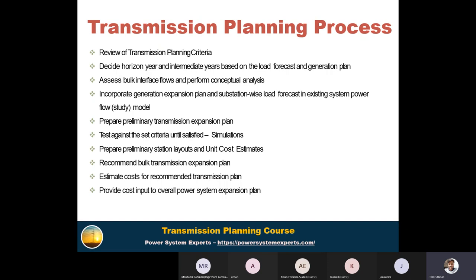But at first, we should have an idea of a preliminary transmission expansion plan, and then test it against the set criteria. So test all these model cases in the software, PSS/E, against those criteria, steady state as well as transient. After that, prepare preliminary station layouts and unit cost estimates, then recommend a bulk transmission expansion plan, estimate the cost for the BOQ, and provide cost input to the overall power system. That is the transmission system expansion plan and transmission system investment plan. All these are the steps required to perform transmission planning. So this is the whole transmission planning process.